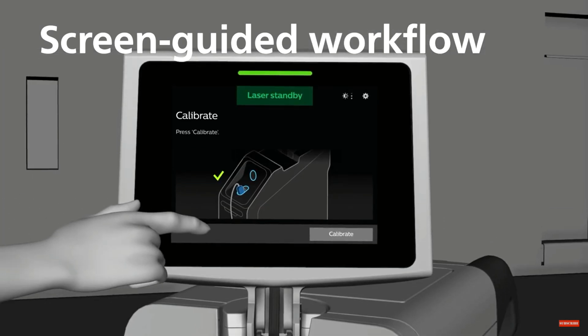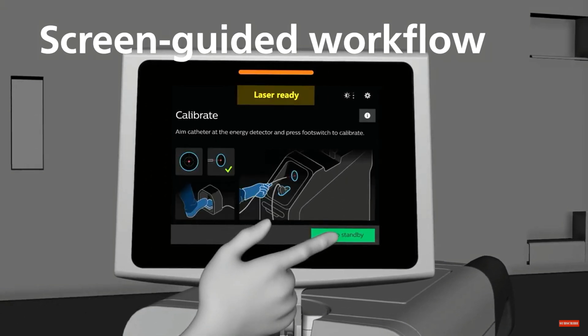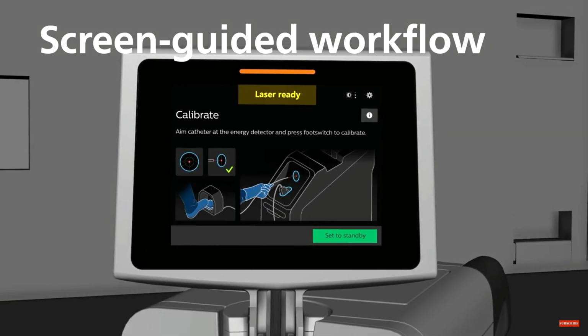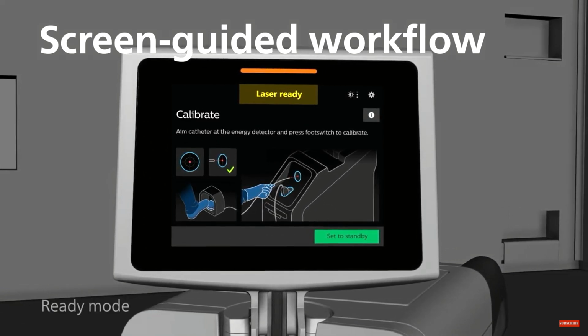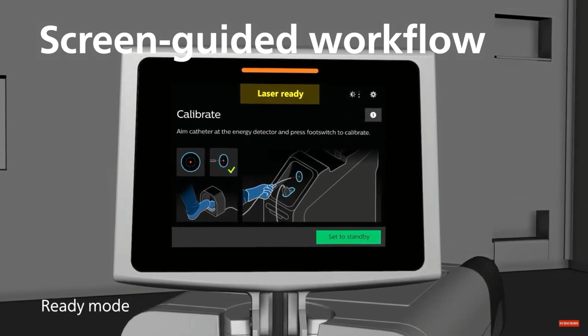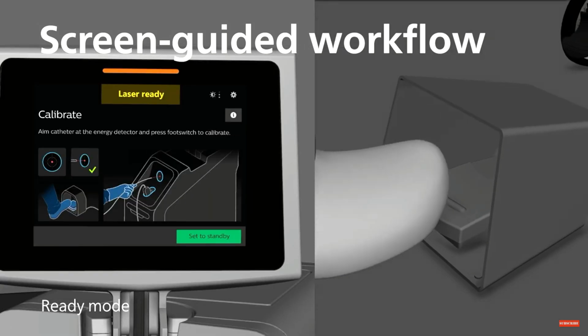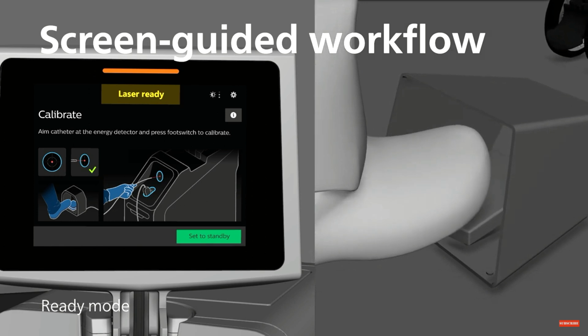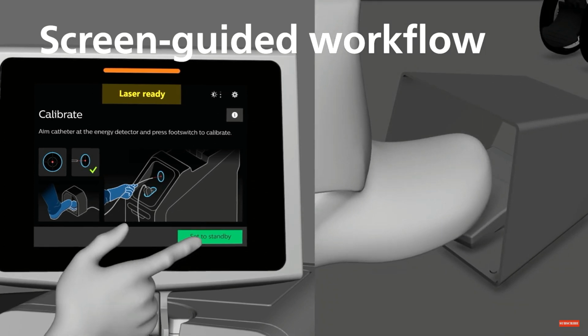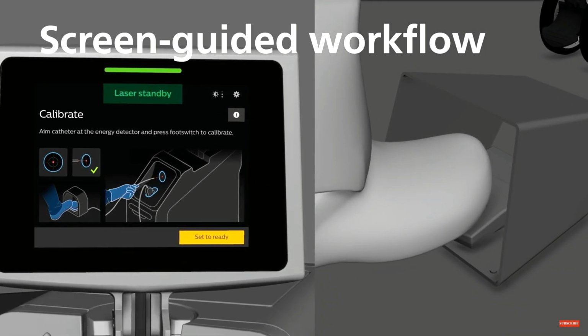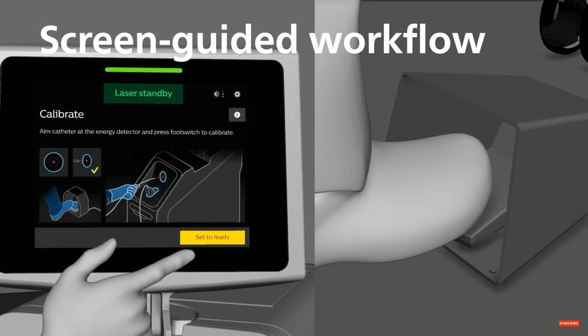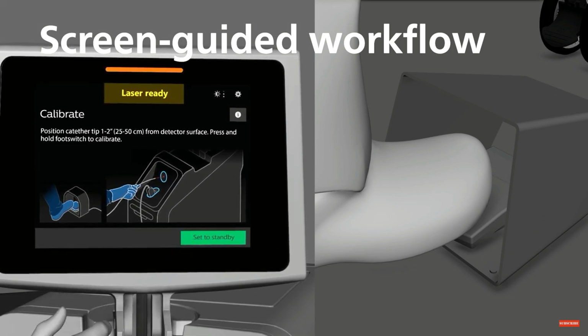To calibrate the catheter, select the Calibrate button on the screen. Once the Calibrate button is pressed, the system enters Ready mode. The system will laze only when the foot switch is pressed while in Ready mode. To enter Standby mode, press Set to Standby. This will disable the foot switch. To continue, press Set to Ready to continue with calibration.